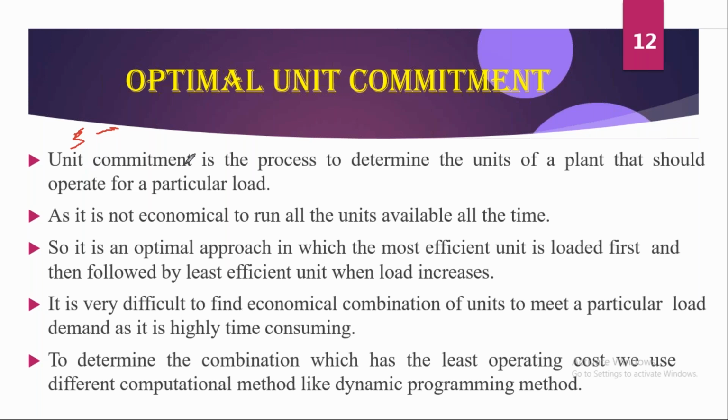See here, unit commitment is the process to determine which units of a plant should be operated for a particular load. Suppose in the morning only 3 units are to be run, and in the evening 2 units. Why? Because from an economical point of view, it is not good to run all available units at all times.